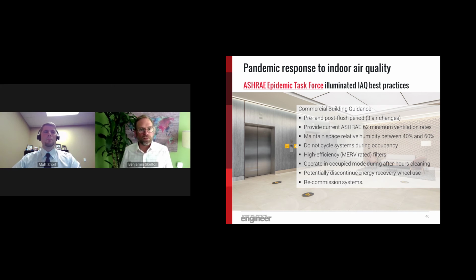And then recommission systems. As we're looking at occupied buildings, existing buildings, they may not have been designed at the time ASHRAE 62 had ventilation standards. They may not be operating as they are intended to. So commissioning and recommissioning is a very critical step.